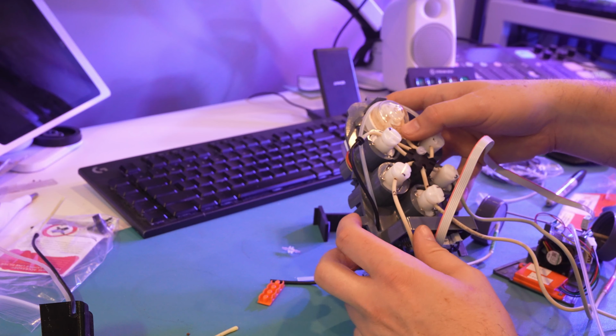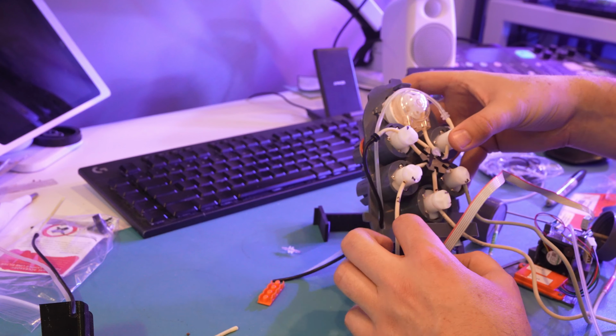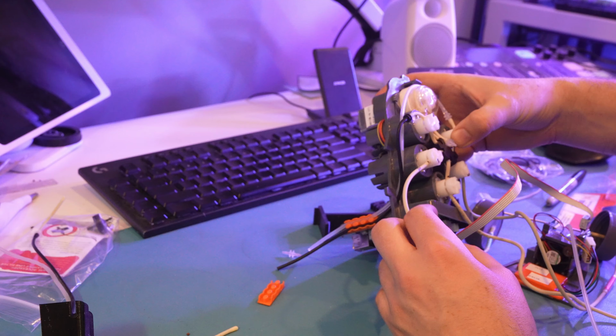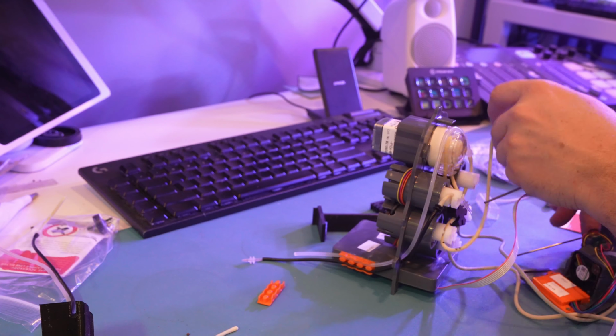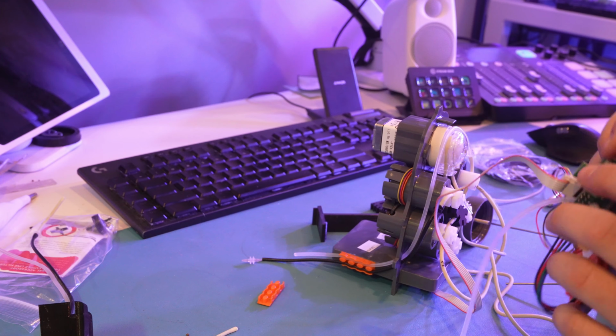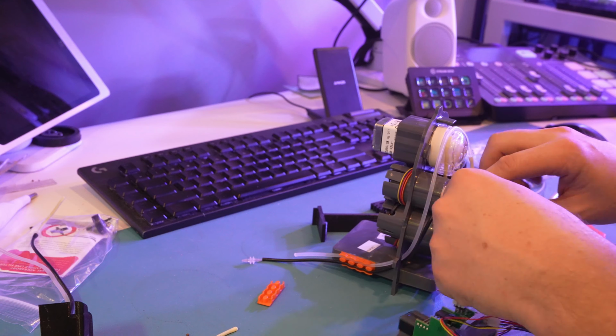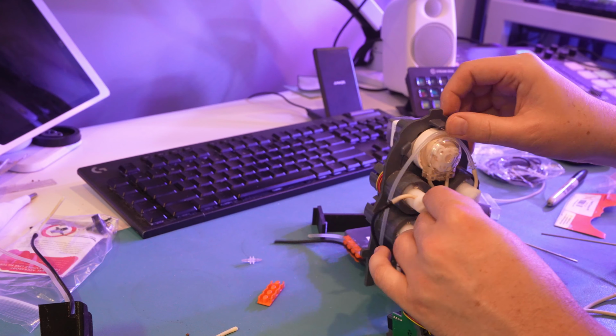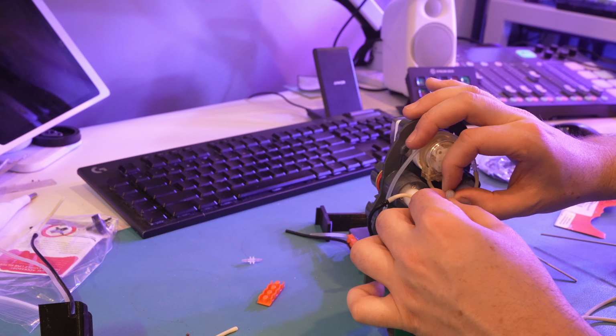Now, in retrospect, I don't think I actually have to remove these cables. I think that was only for if it was in the housing. So I guess a little bit of a bonus if you have the DIY housing version. And now reconnecting our cuvette just connects right to the outside of our pump head motor. So super easy to reconnect this guy.